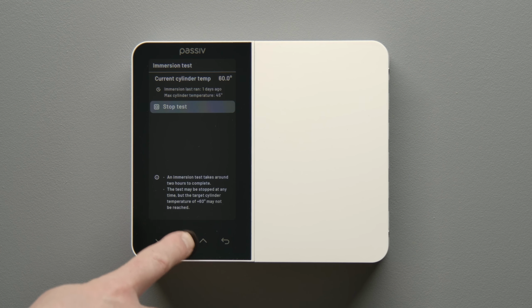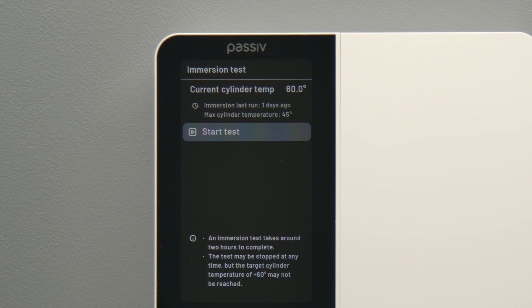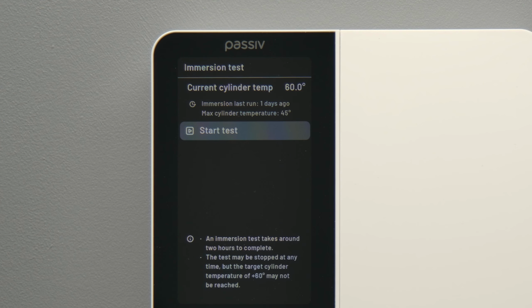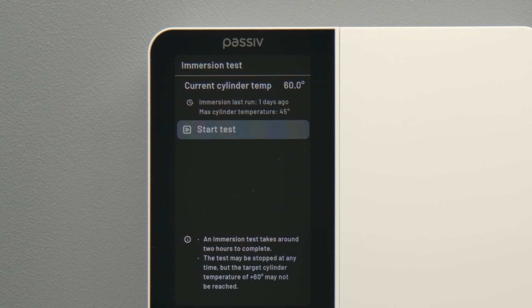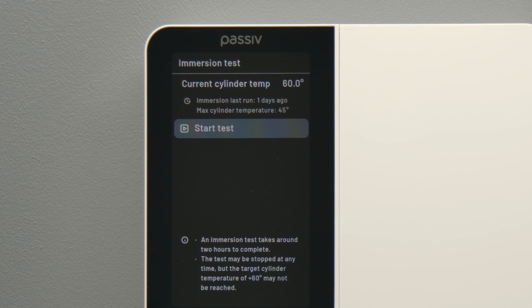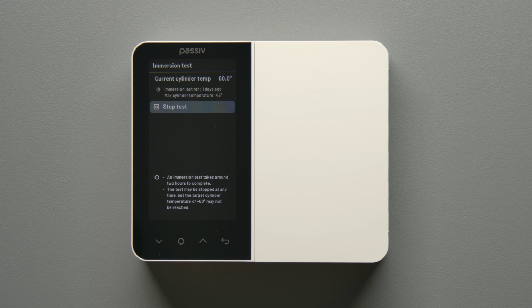The result of the test will be stored on the programmer until either the test is rerun or an anti-Legionella cycle automatically runs. If the test fails to reach 60 degrees Celsius, this could be an issue with the immersion element and its high temperature thermostat. Ensure that the immersion element will be able to reach 60 degrees Celsius, as this is essential for the safety of the system.